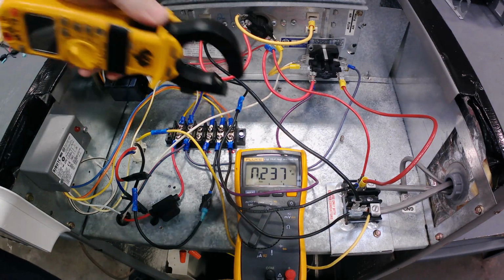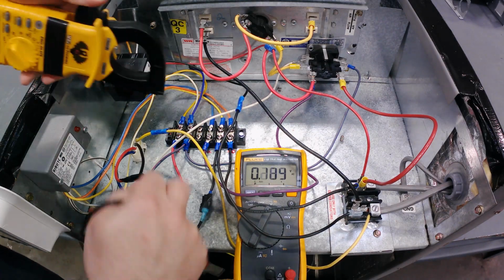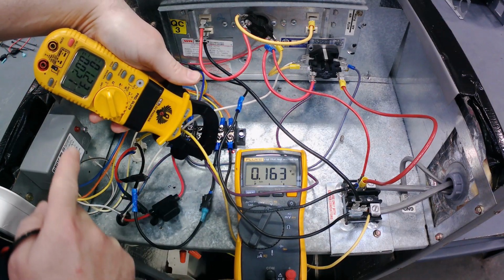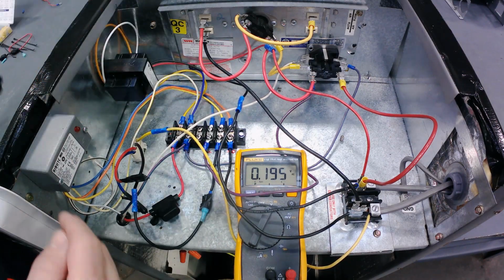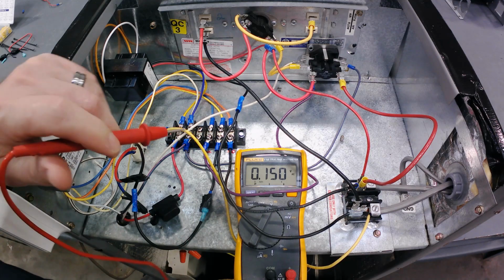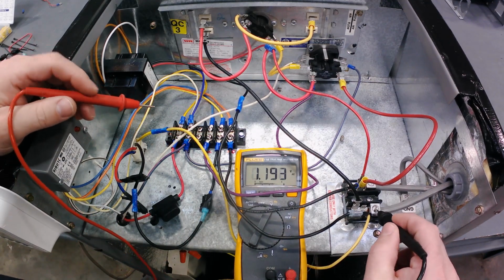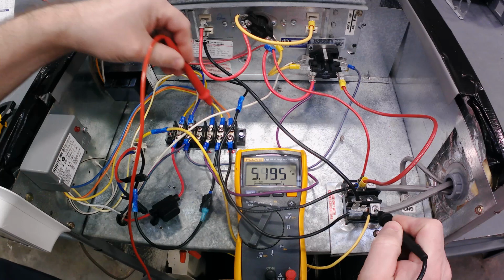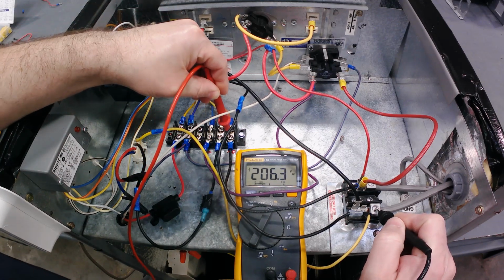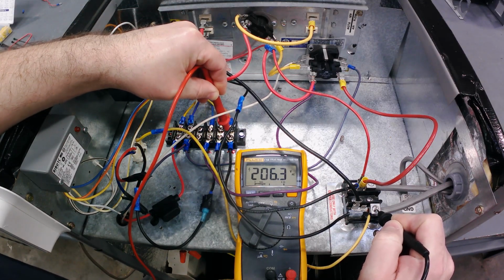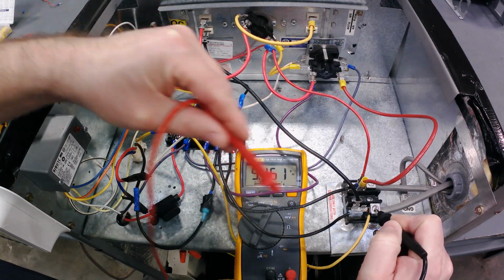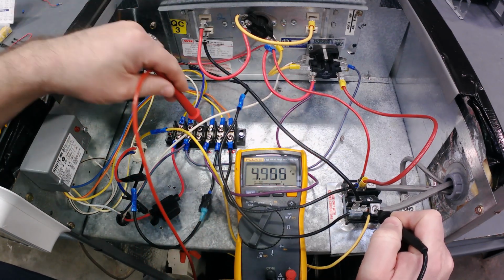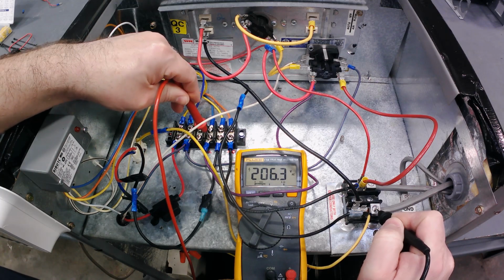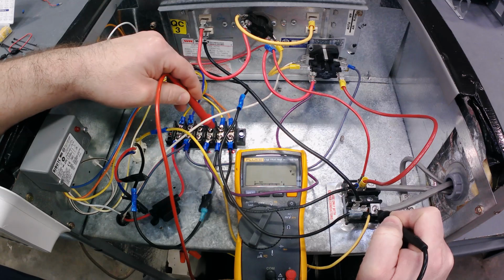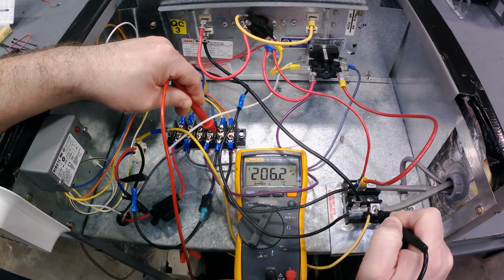For my fan, there's the yellow right there, I'm going to have 1.23. So as far as function, we wired it in right. And now what will happen is if I go on my L2 terminal block and I check here, I've got 208. But only because it's already plugged into the terminal. All right, look at what happens with the purple. I've got 208 as well, or 206, and of course my common's going to have 208, 206, something like that.